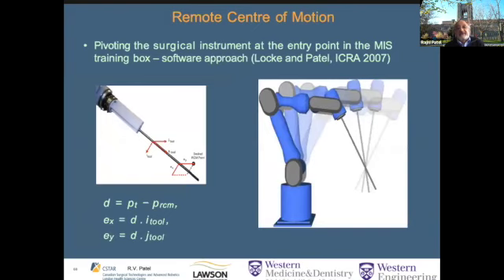Now, one of the things that we also did with this test bed was to create a remote center of motion. If you recall, the instruments are inserted into the body through small incisions, so that when the surgeon manipulates the instruments, they are pivoted about the point of entry. This means that we have to create a pivot point at the entry, or what would be the entry, to the body. And this is done through what is called a remote center of motion. So essentially, this is generated through software.